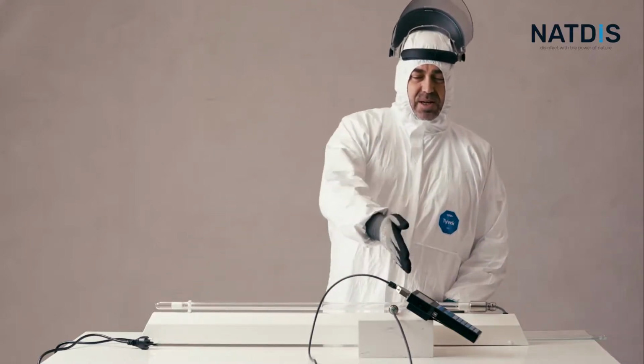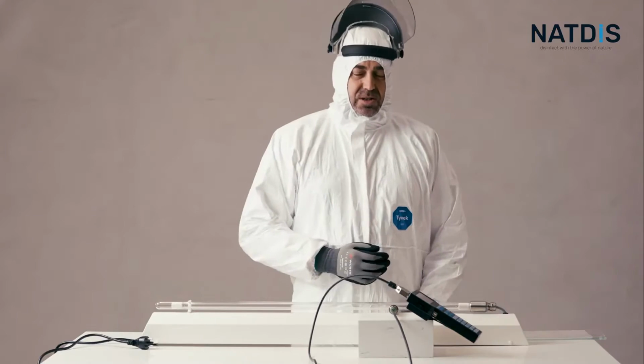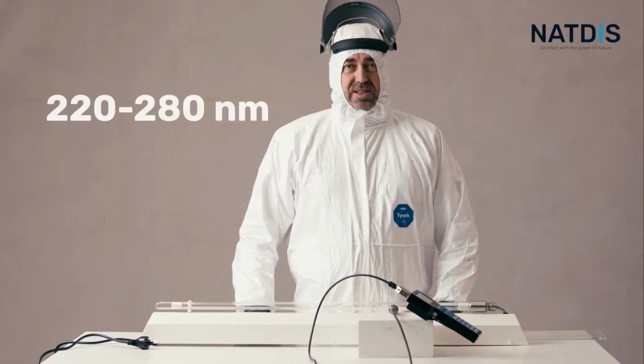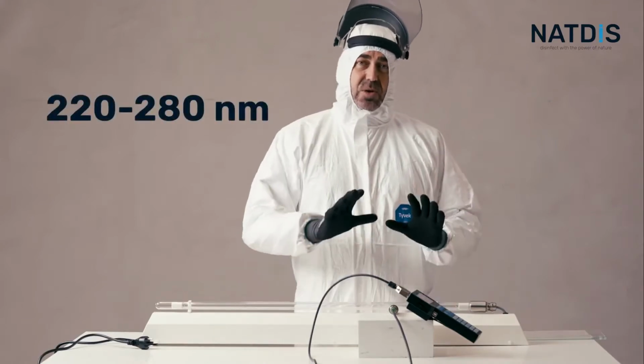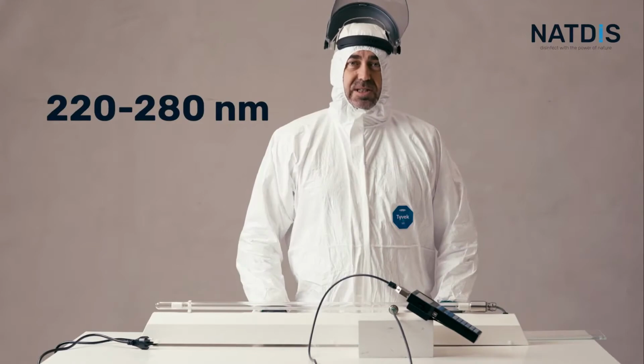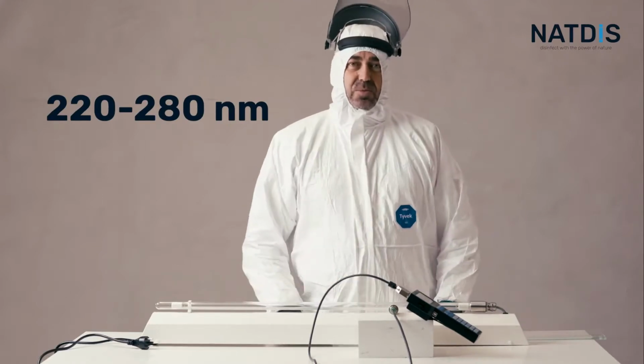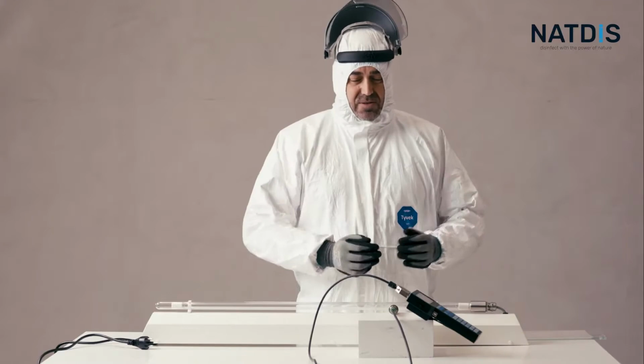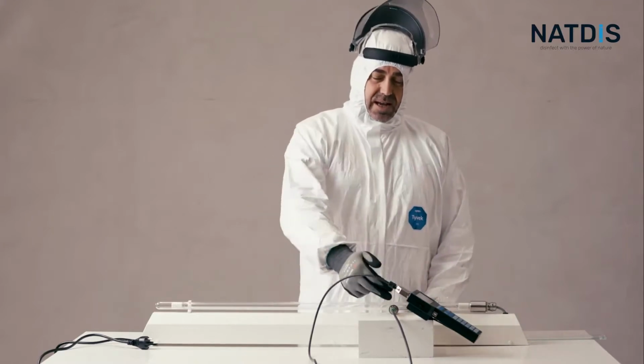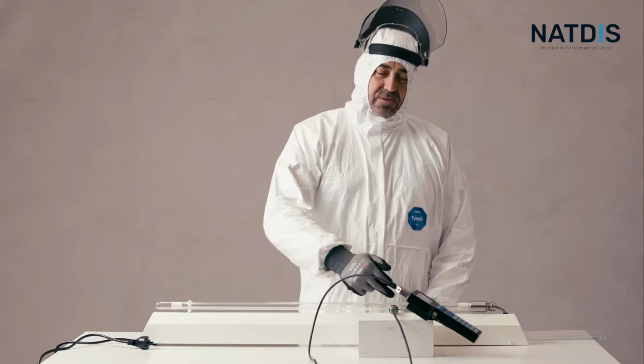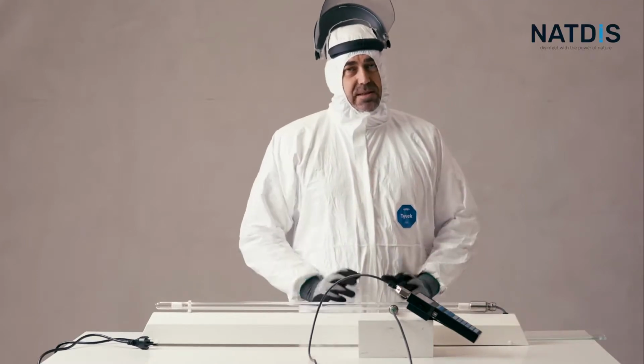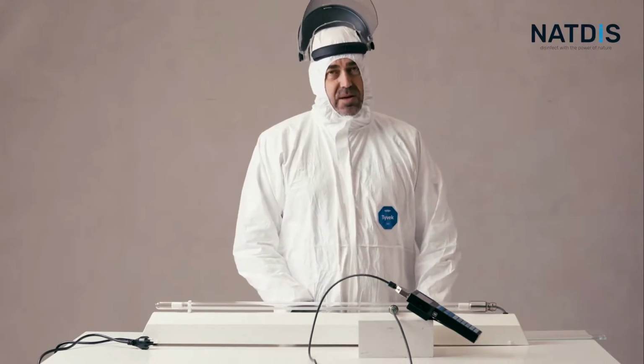For this purpose, I have my UVC meter here, which is a radiometer connected to a probe that measures UV from 220 to 280 nanometers. And it's important to know your measuring equipment when working with UVC. The probe must be approved and calibrated for the range you want to measure, and the radiometer itself must be designed for that purpose. And that's the kind of setup we have here. That means when I turn on the lamp now, my probe measures the UV from the lamp, and I get a value in watts per square meter on the radiometer's display. Then I can see how the different things work, which I will demonstrate now.